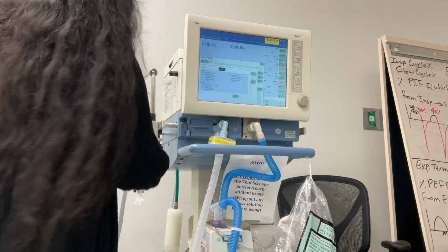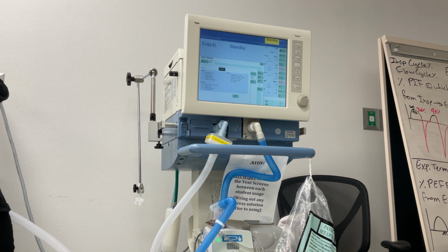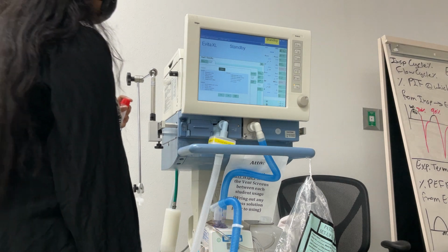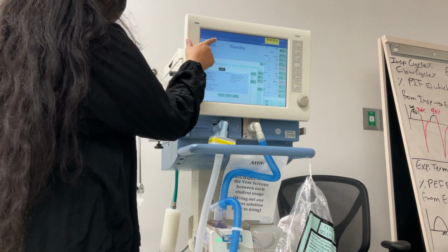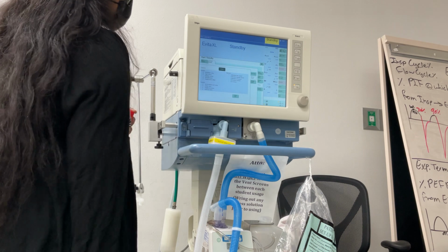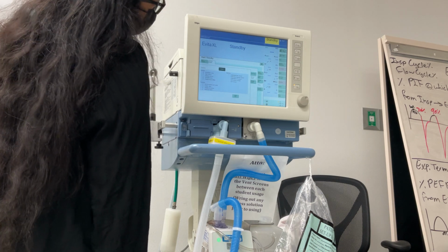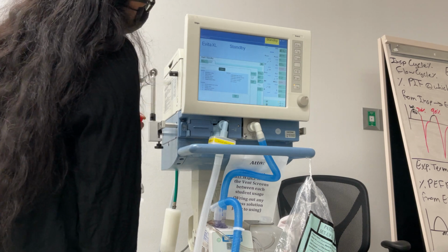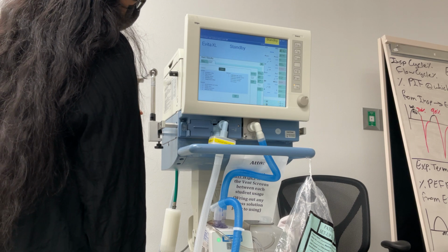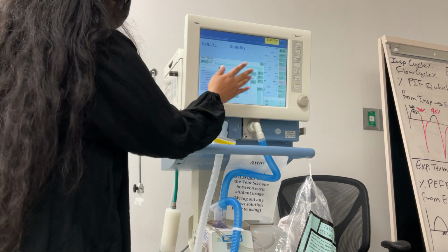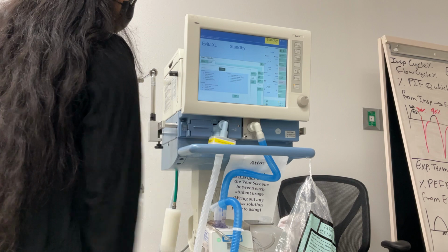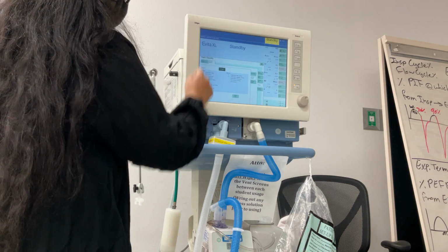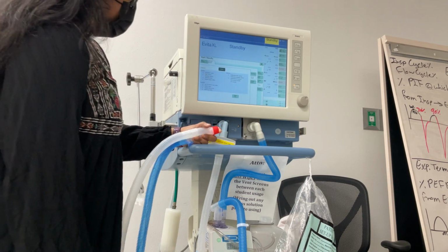Okay, connect air and oxygen supply. Connect. So audible alarm sound check. You hear it? Yes. Now it's going to do the flow calibration. It said it's okay. Disconnect CL NeoFlow sensor, press this. We're not doing anything with neonate, so just next test. It's gonna say it was aborted. Now it's gonna do an O2 cal.